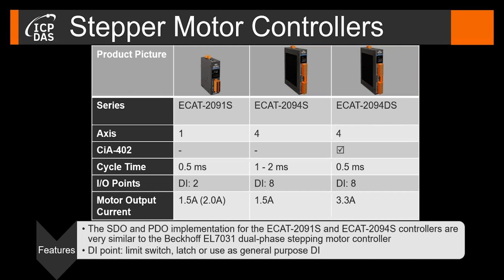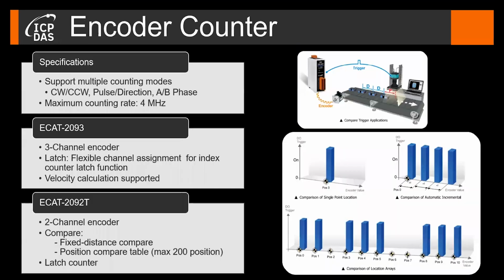The ECAT 2094DS is our newest controller type on the market and supports a current of 3.3 ampere, as well as CiA 402 defined motion profiles. We provide 2 and 3 channel encoders. Multiple counting modes are supported, such as clockwise, counterclockwise, pulse direction, AB phase, etc. A maximum count rate of 4 MHz is supported. It has a built-in hardware latch, which can be used for homing and measurement purposes.